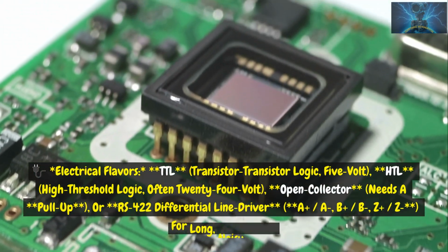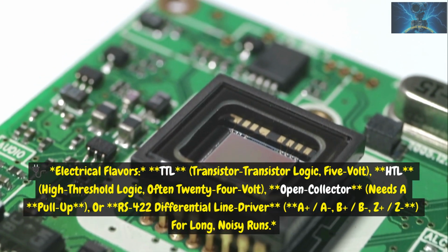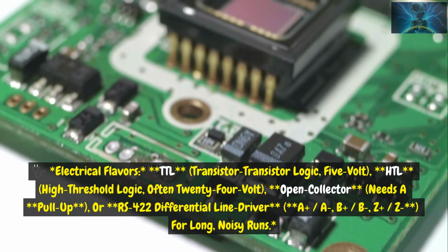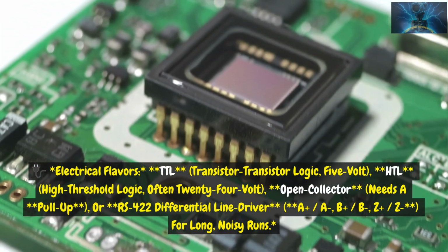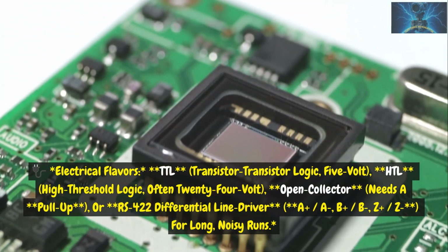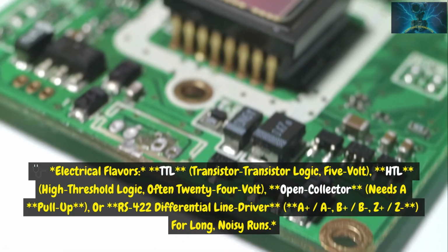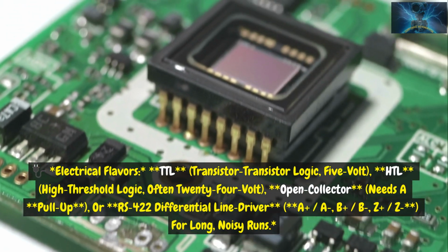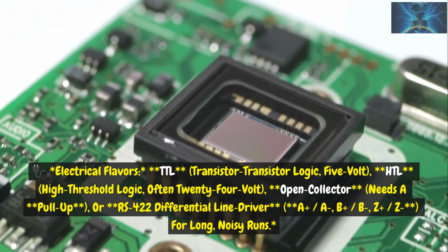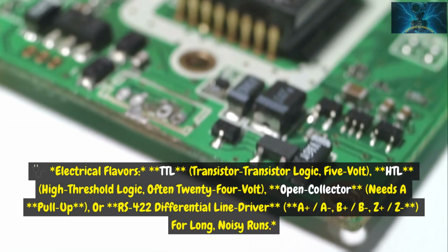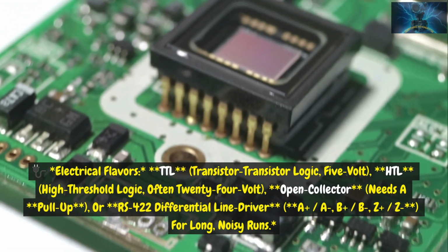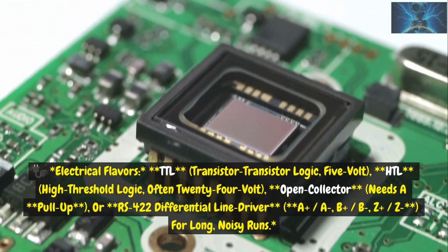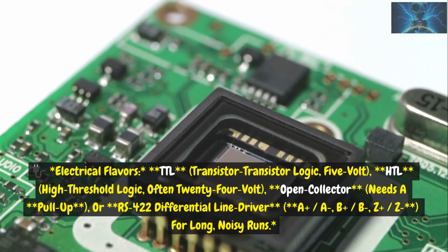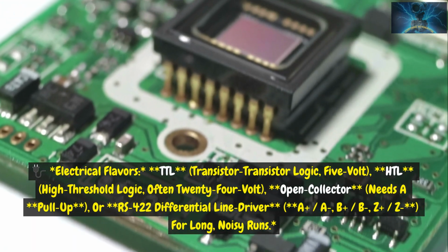Electrical flavors. TTL, transistor-transistor logic, 5 volt. HTL, high threshold logic, often 24 volt. Open collector, which needs a pull-up, or RS422 differential line driver: A plus, A minus, B plus, B minus, Z plus, Z minus, for long, noisy runs.